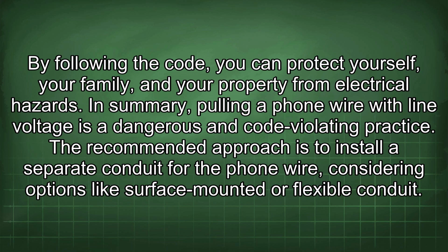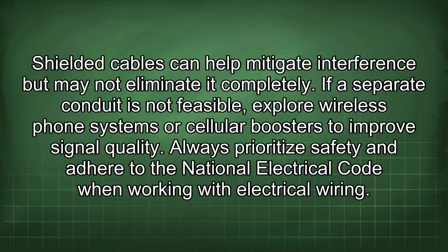In summary, pulling a phone wire with line voltage is a dangerous and code-violating practice. The recommended approach is to install a separate conduit for the phone wire, considering options like surface-mounted or flexible conduit. Shielded cables can help mitigate interference but may not eliminate it completely. If a separate conduit is not feasible, explore wireless phone systems or cellular boosters to improve signal quality. Always prioritize safety and adhere to the National Electrical Code when working with electrical wiring.